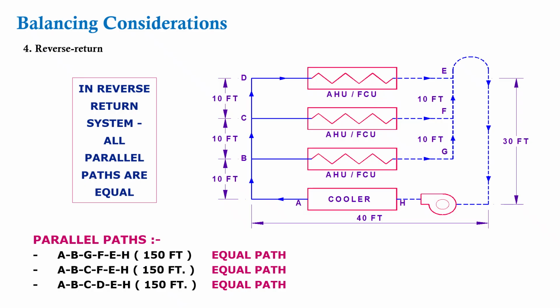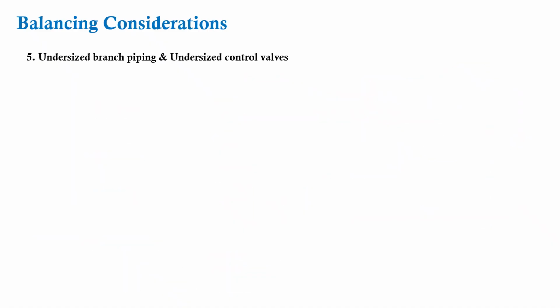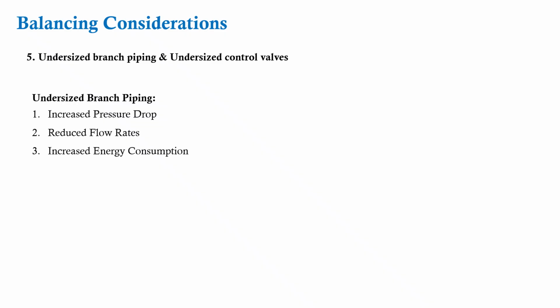Now the pressure independent balancing valve, which I had already mentioned, is a great methodology to control the flow. Undersized branch piping or control valves: let me share with you the pros and cons of undersized piping and control valves. Let's first discuss the undersized branches or piping. It increases the pressure drop, and if there is an increase in the pressure drop, it's going to add energy loss. The second, it reduces the flow rate. The third, an increase in energy consumption, which I had already mentioned.